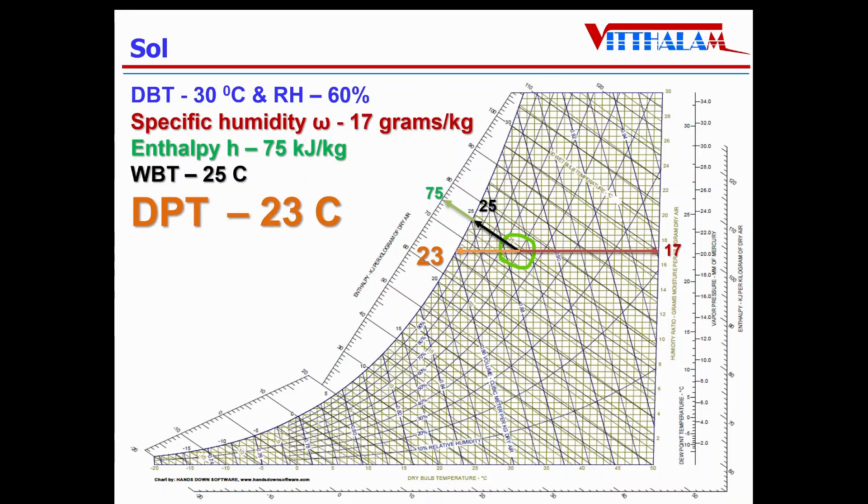That means if such air will bring in the contact of any surface having a temperature less than 23 degrees Celsius, the condensation will start. Or in other words, if I want to reduce the moisture content of the given air by cooling, I have to cool this air at least to the tune of 23 degrees Celsius.